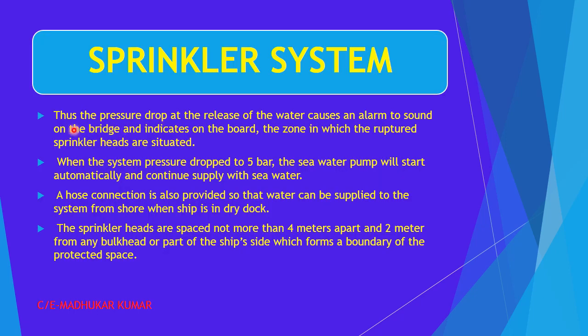Now further to it, the pressure drop at the release of the water causes the alarm to sound. We have just seen that, and this will indicate on the bridge on board, and the zone in which the sprinkler head has ruptured is also described. That means the sprinklers are divided into different zones, so when it is operated, the audio visual alarm for that particular zone will come.